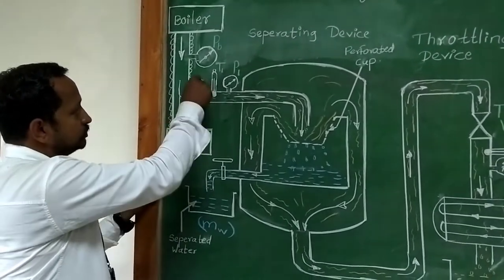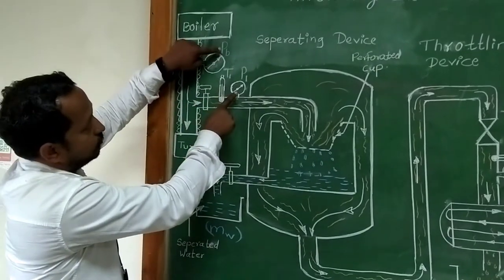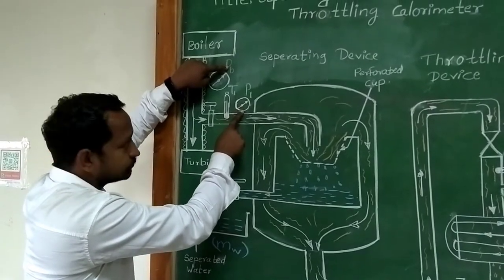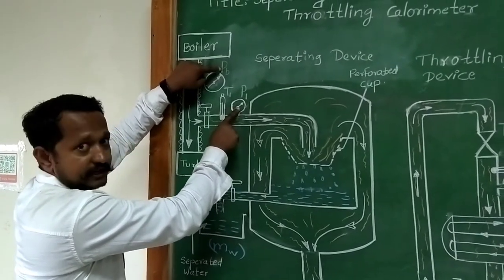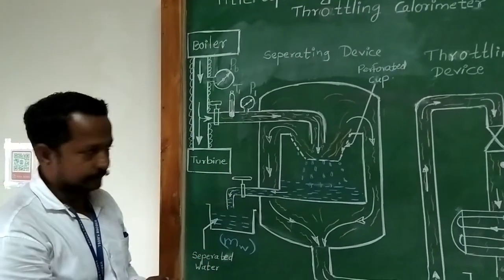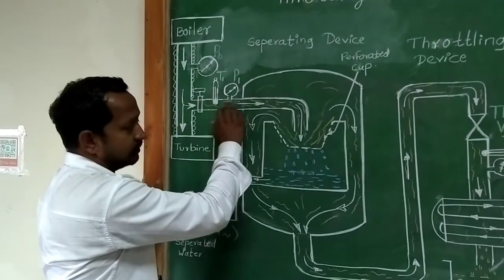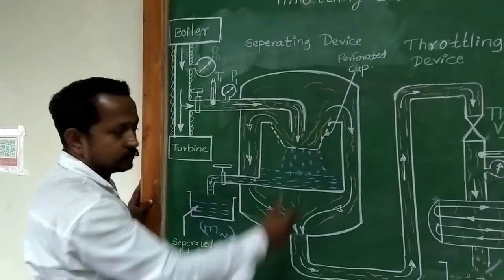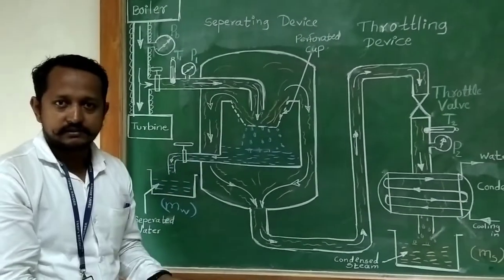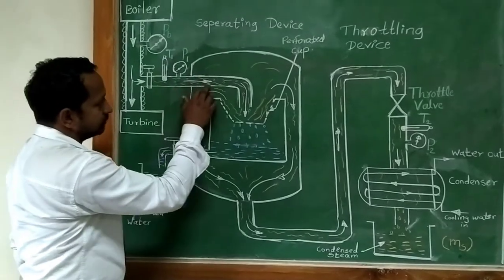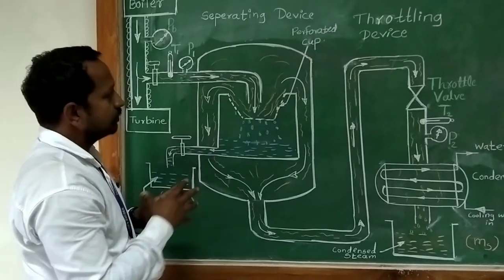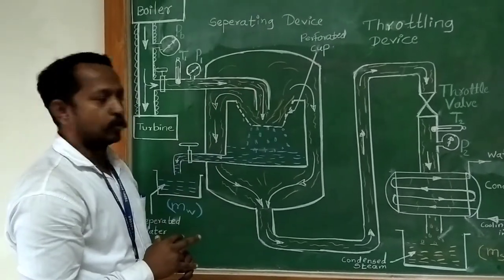To check that, one should ensure when this valve is open, one should focus on the pressure of the boiler as Pb, and pressure of the line as P1. Once these pressures are equal, we can say there is no throttling — there is no pressure difference, there is no throttling. Hence, this steam, which is taken as a sample steam for checking of its dryness fraction, consists of wet particles and dry steam. As you can see here, some blue dots and some orange lines, which show steam and water particles.